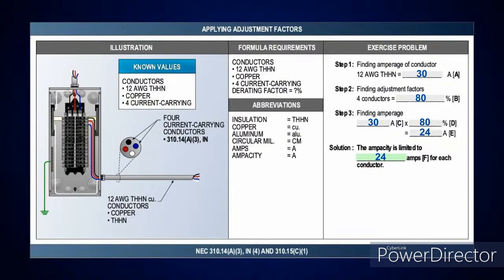Okay? Now, if I look at this as THHN, and I'm in the 90 degree C column for number 12 per Table 310.16, it's going to tell me it's good for 30 amps. And then if I'm looking at the adjustment factor, I'm going to go over and look at Table 310.15(C)(1), and it'll tell you four or more current carrying conductors, it'll say 4 to 7, you're going to have an 80% derating factor. So you take the 30 amps times 80%, and that'll give you 24 amps.